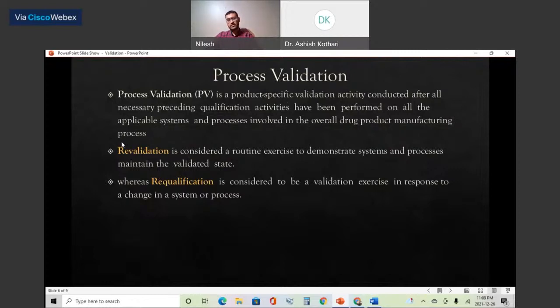And for revalidation, there are two terminologies: revalidation and requalification. Revalidation is a routine exercise. That is what I said. Once you generate the risk assessment, you decide that the product and the equipment has a high risk. You have to revalidate either every 6 months or annually. At that time, you have to compare your revalidation activity to the original qualification, the original validation activity. If something is different from your original validation, then you have to redesign your product, or in case of equipment, you need to improve the frequency of the preventive maintenance.